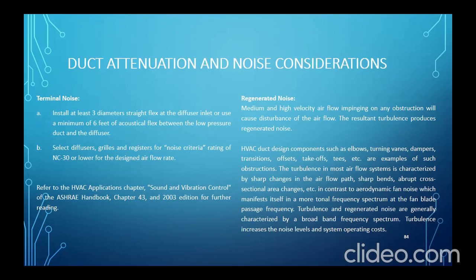Regenerated noise. Medium and high velocity airflow impinging on any obstruction will cause disturbance of airflow. The resultant turbulence produces regenerated noise. HVAC duct design components such as elbows, turning vanes, dampers, transitions, offsets, takeoffs, etc. are examples of such obstruction.